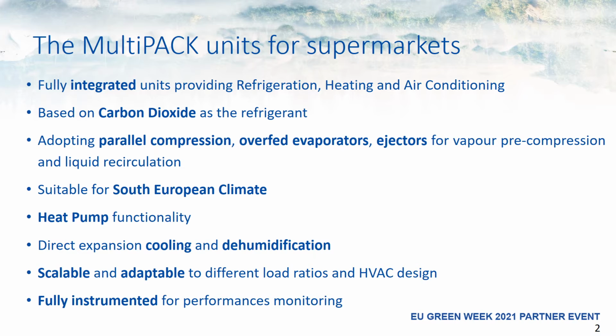They have integrated heat pump functionality to provide all the thermal service required during the winter time, and they provide cooling and dehumidification with direct expansion. These units are scalable and adaptable to different load ratios and to different design of the heating, ventilation and air conditioning system. And finally, they are fully instrumented for performance monitoring.